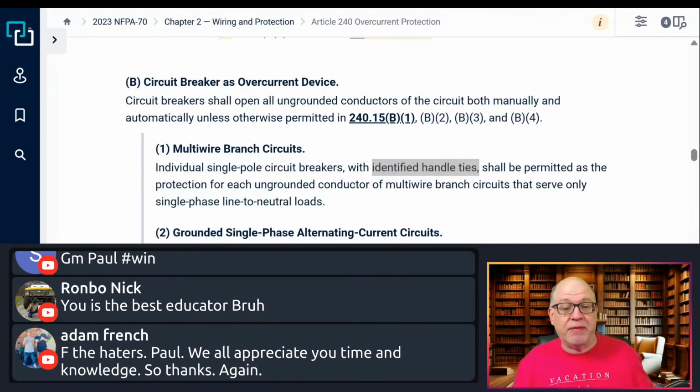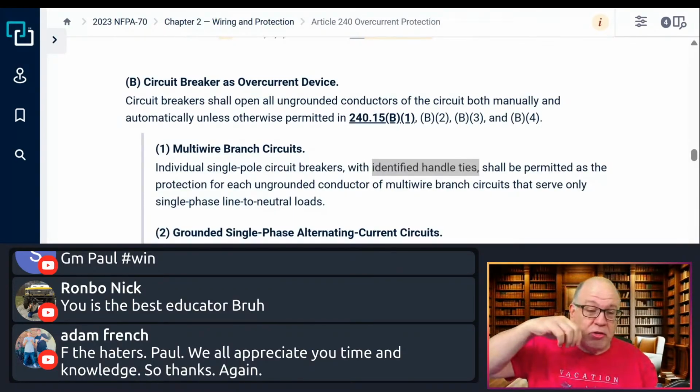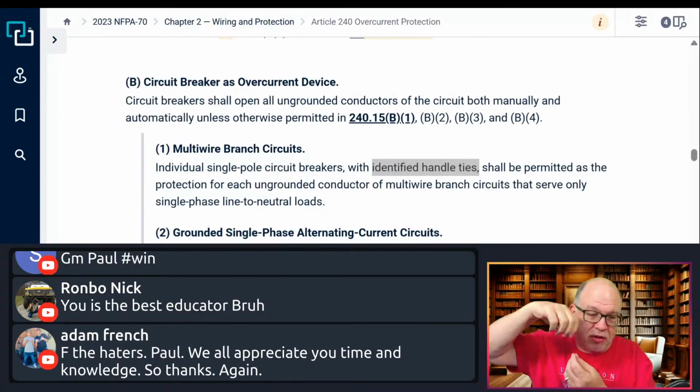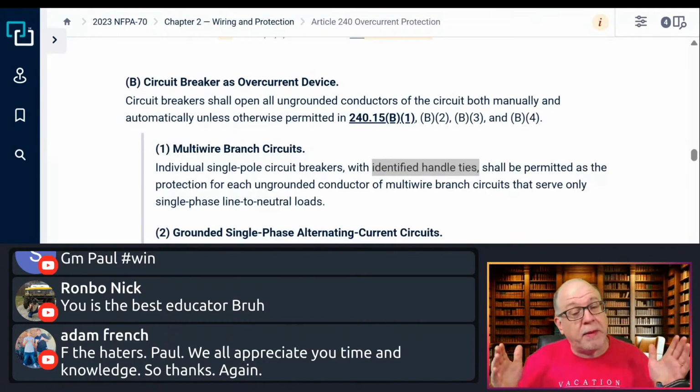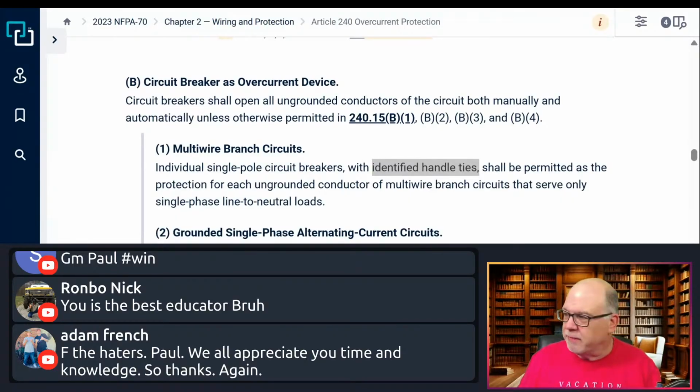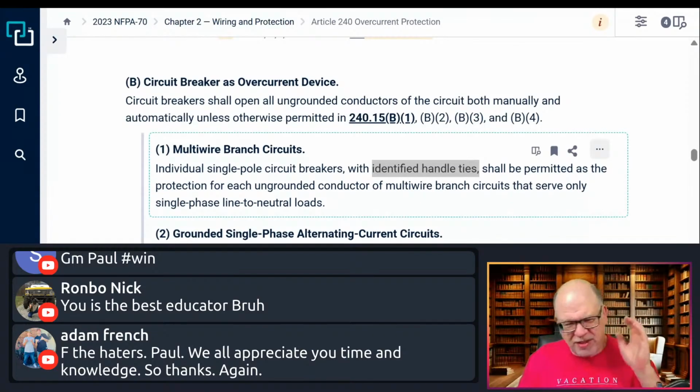Even though you're right, some things may work better. A 6-32 with a nut on each end, tightened down, or even an 8-32 probably works better than all of them. But it's not identified for it, so we can't accept it. And I don't want any of the liability involved, especially if that causes any damage. You get what I'm saying?